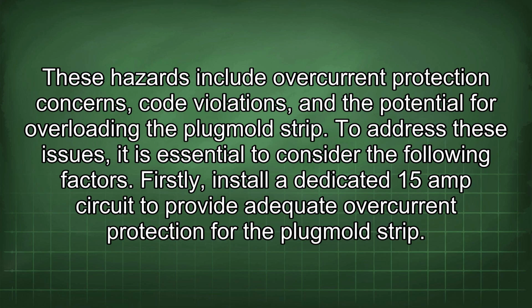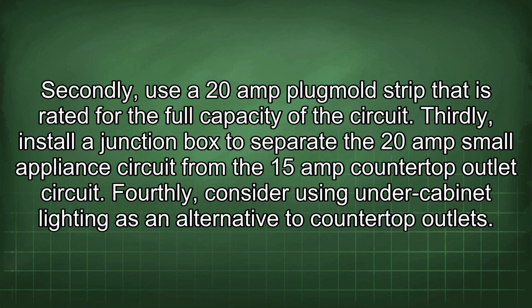To address these issues, it is essential to consider the following factors. Firstly, install a dedicated 15 amp circuit to provide adequate overcurrent protection for the Plugmold strip. Secondly, use a 20 amp Plugmold strip that is rated for the full capacity of the circuit. Thirdly, install a junction box to separate the 20 amp small appliance circuit from the 15 amp countertop outlet circuit. Fourthly, consider using under-cabinet lighting as an alternative to countertop outlets.